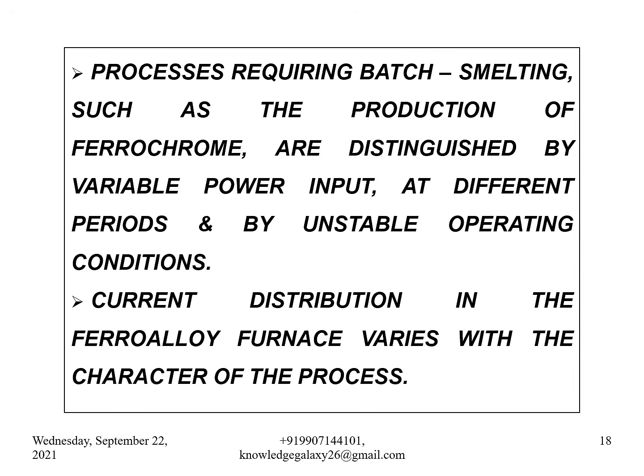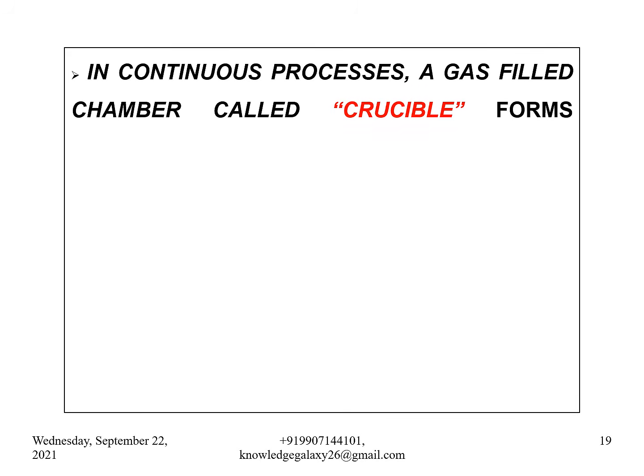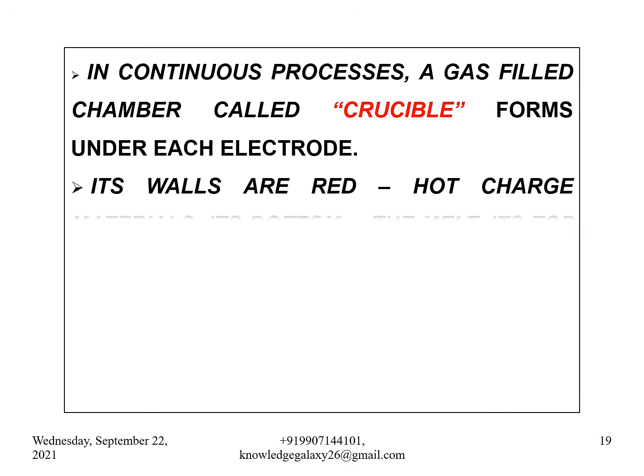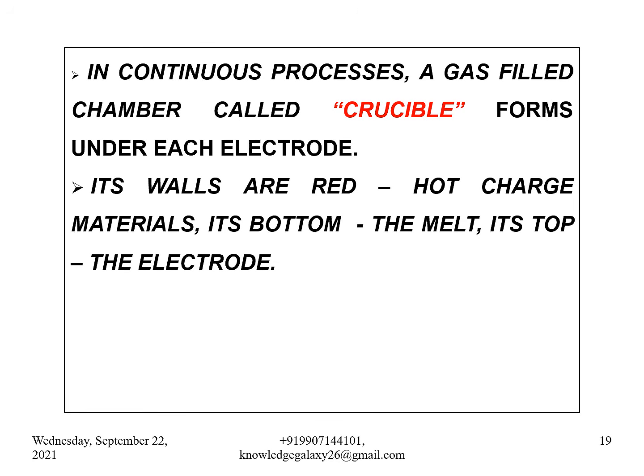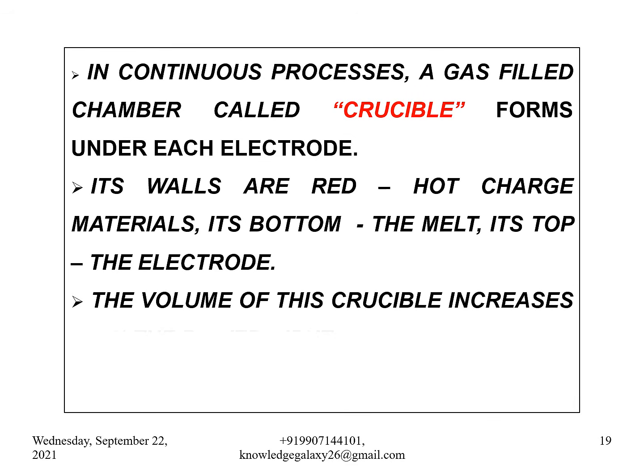Current distribution in the ferroalloy furnace varies with the character of the process. In continuous processes, a gas-filled chamber called a crucible forms under each electrode. Its walls are red-hot charge materials, its bottom is the melt, its top is the electrode. The volume of this crucible increases with the power input. This is a schematic representation of the crucible which is formed under the electrode, where the charged material gets melted by the heat generated by the electrode's electric arc.